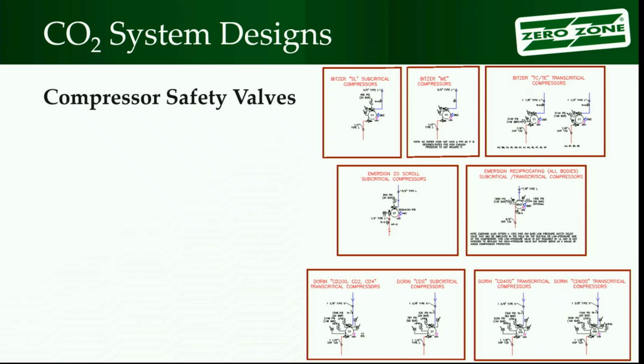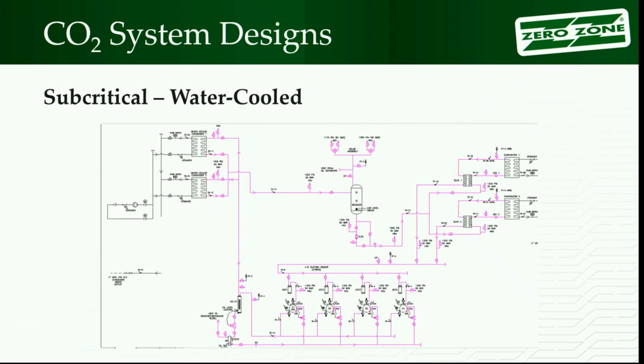That valve's there should you have some oddity, and it's got to be pretty odd to have the high pressure safety release on a compressor. You've got a high pressure cutout. Software is going to try to turn it off, but it's just something to be aware of. These are different, so I'm just laying out the differences because it's something to know.